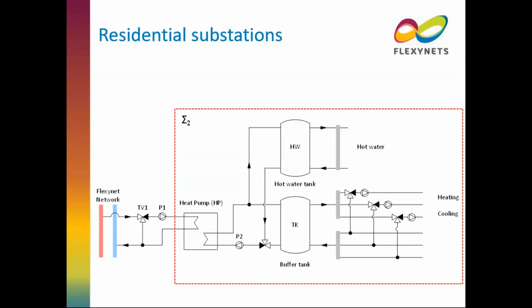On the side of the building, on the right-hand side of the heat pump, it's important to stress the presence of local thermal energy storages, especially the one for domestic hot water preparation. This is a key condition when one has a heat pump, because instantaneous production of domestic hot water is not so easily possible with a heat pump.